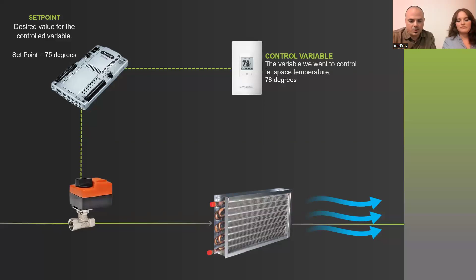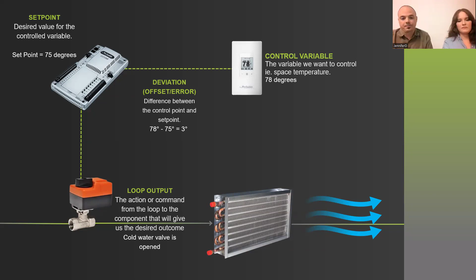From there, we can get into the deviation. The deviation is the difference between where your set point is and where your control variable is. In this case, we have a 78 degree temperature and a 75 degree set point. That gives us a deviation of 3 degrees. That is ultimately going to relate to how severely we respond through the control loop output. In this case, this is going to be a chilled water valve. It's going to open and close based on how large our deviation is from the set point.